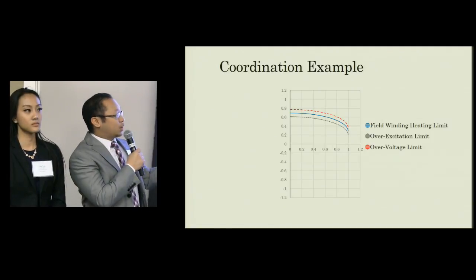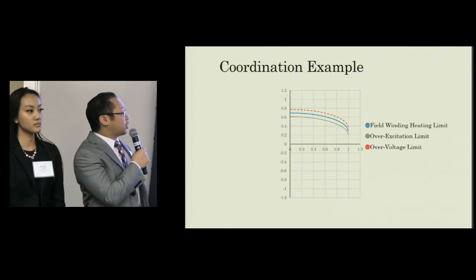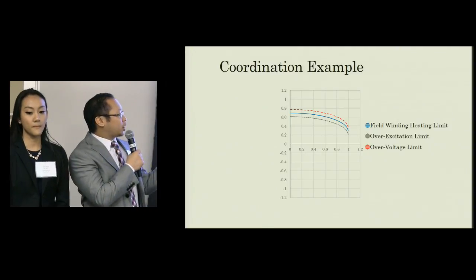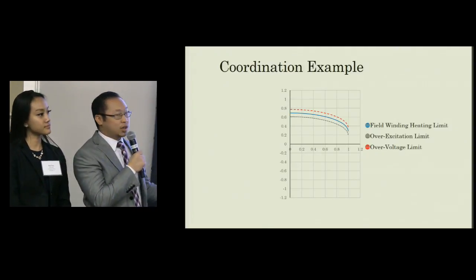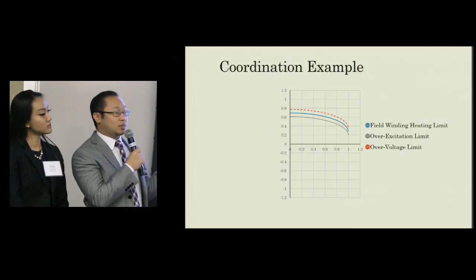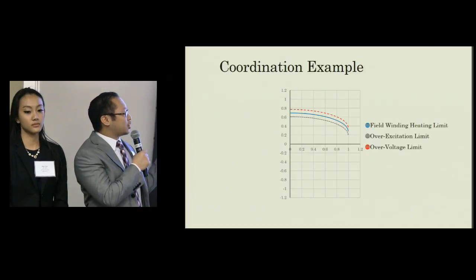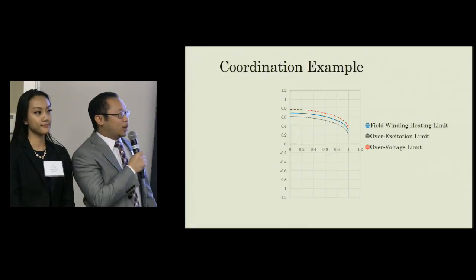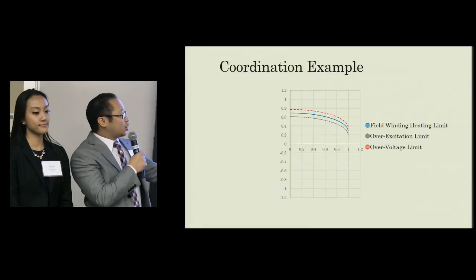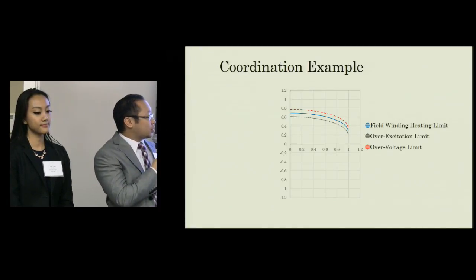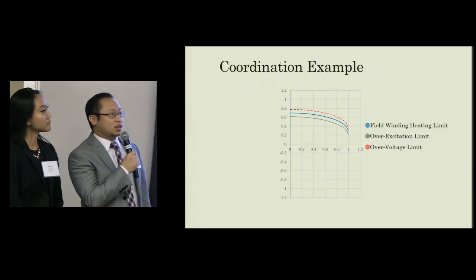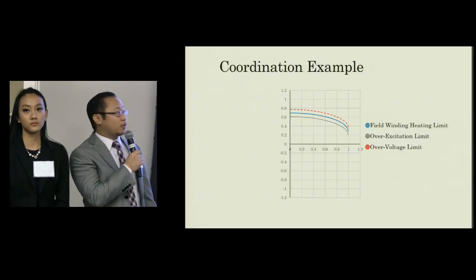You have the field winding heating limit in blue, and that is a physical property of the generator. So we can coordinate the overexcitation limiter in gray to be slightly underneath, because it limits the operating region of the generator. And if that overexcitation limit fails, we have an overvoltage limit in red, which prevents the generator from operating at high voltage for too long.